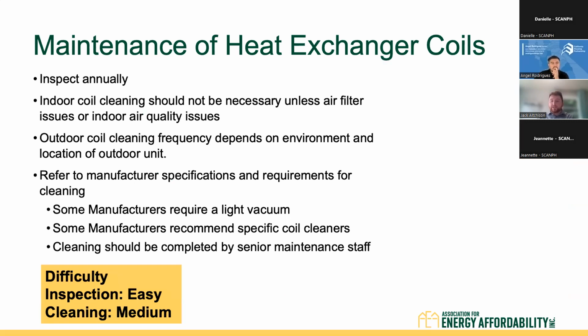You should be inspecting these annually. Indoor coil cleaning should not be necessary unless you have air filter issues or indoor air quality issues. Ultimately, your indoor coil is protected by your air filter. If you are properly maintaining your air filter, you should not have to clean your indoor coil. It should be protected by that air filter and should basically stay pristine throughout the useful life of the HVAC equipment. Outdoor coil cleaning frequency depends on the environment and location of the outdoor unit.